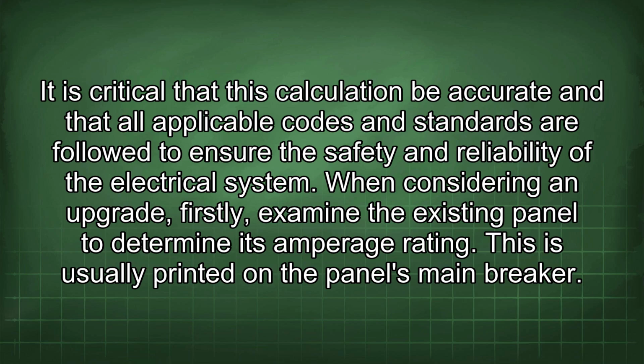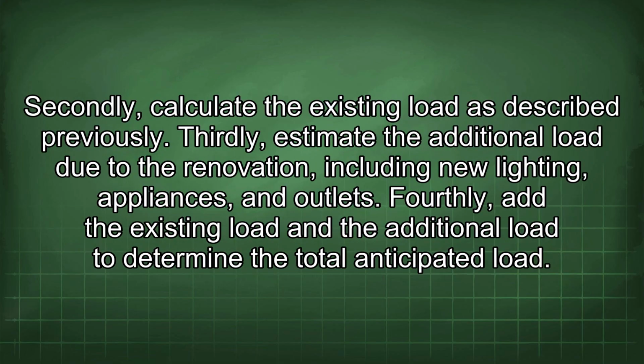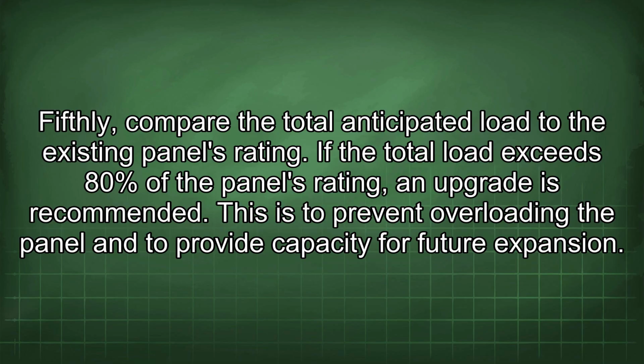When considering an upgrade, firstly, examine the existing panel to determine its amperage rating. This is usually printed on the panel's main breaker. Secondly, calculate the existing load as described previously. Thirdly, estimate the additional load due to the renovation, including new lighting, appliances, and outlets. Fourthly, add the existing load and the additional load to determine the total anticipated load. Fifthly, compare the total anticipated load to the existing panel's rating. If the total load exceeds 80% of the panel's rating, an upgrade is recommended. This is to prevent overloading the panel and to provide capacity for future expansion.